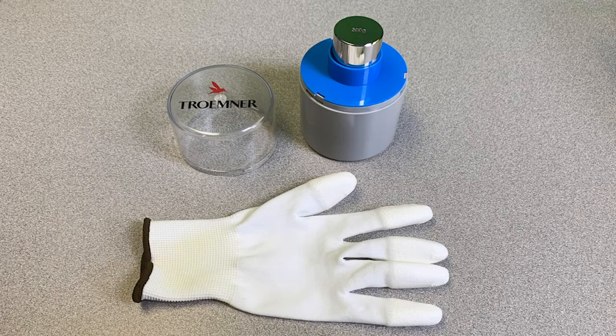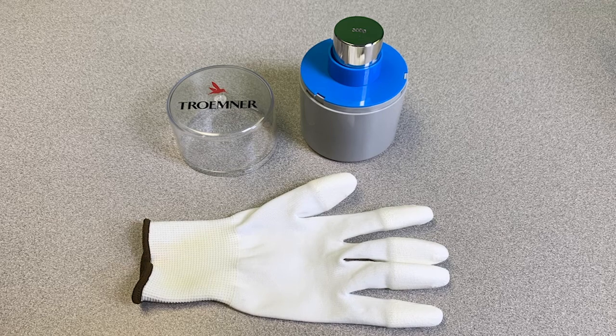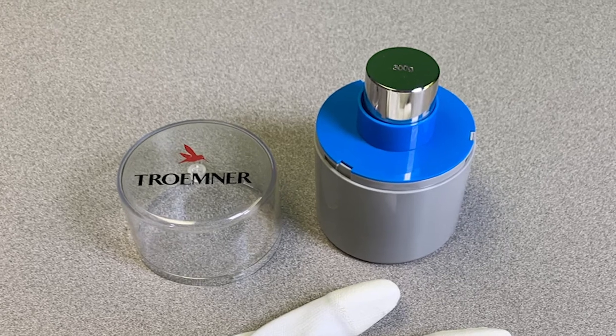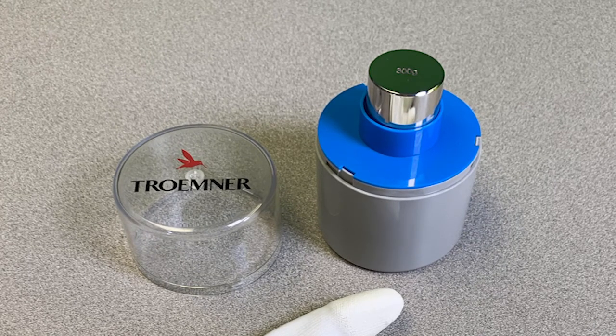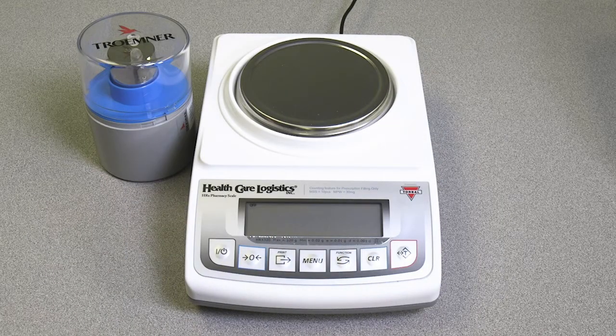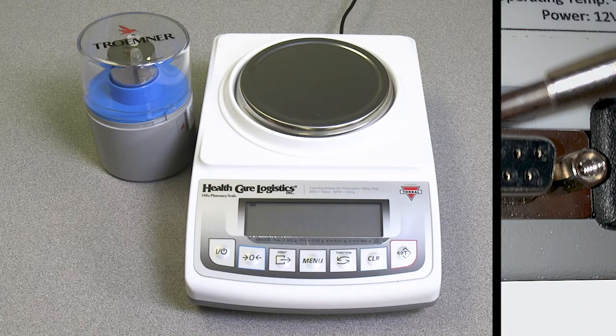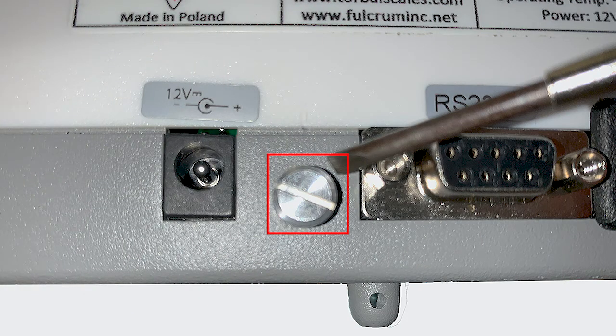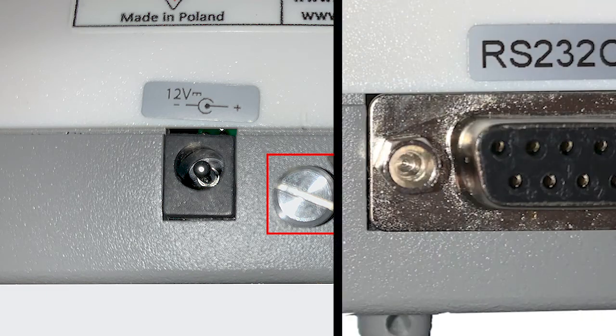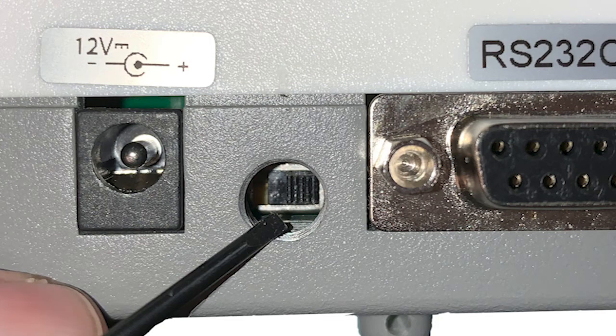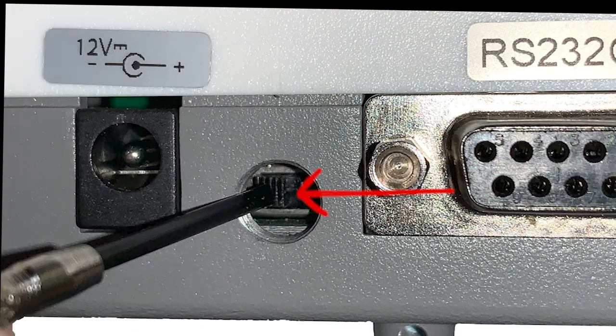If you purchased an external calibration scale or you wish to manually configure the internal calibrating scale, you will need to use a certified weight that does not exceed the weight requirement of the scale. Begin by making sure there is nothing on the pan and the scale is stable. Use a flathead screwdriver and gently remove the calibration screw located in the rear of the scale. When the screw is removed, use a pointy device, such as the end of a paperclip, to toggle the switch to the left, which is the on position.